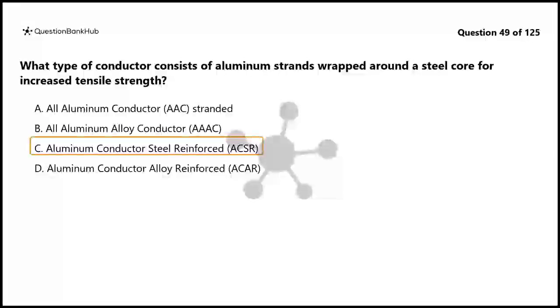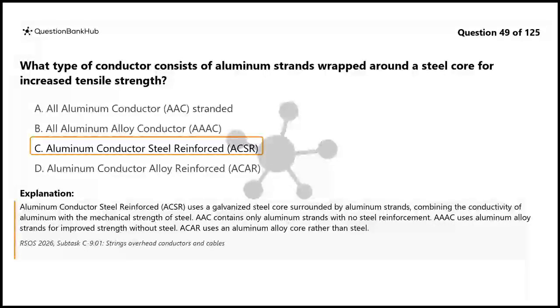The correct answer is C. Aluminum conductor steel reinforced, ACSR, uses a galvanized steel core surrounded by aluminum strands, combining the conductivity of aluminum with the mechanical strength of steel. AAC contains only aluminum strands with no steel reinforcement. AAAC uses aluminum alloy strands for improved strength without steel. ACAR uses an aluminum alloy core rather than steel.